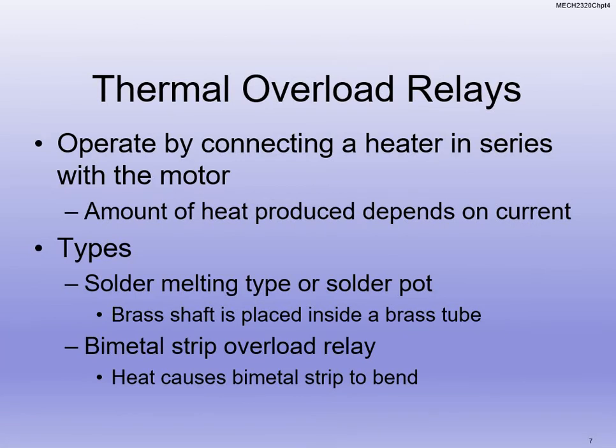So if we use a thermo overload relay, very common here, we connect the heater in series with the motor. So the amount of heat on that depends on the current. Remember, as current goes through a wire, it gives off heat. When you have a little space heater, those are just coils of wire, and you're putting current through them, and that's why they glow and give off heat. Same if you have an electric stove. That's just a coil of wire essentially, and you're heating it up, doing the same thing.